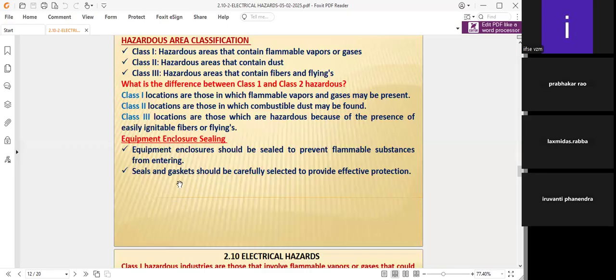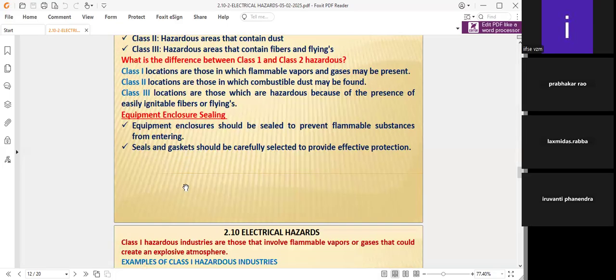Because of the heating lines, heating elements and heating element wiring are there, and the pipeline is always under warm condition. At that condition, gaskets, flange joints, or seals have to be selected very carefully. It is not simply the normal temperature condition. We have to withstand the temperature because the heating elements are there over the pipelines, the steam lines and all. You have to see that gaskets and seals are carefully selected for effective protection. It is definitely mentioned in the manufacturer manual itself.